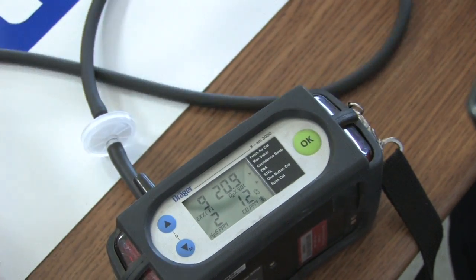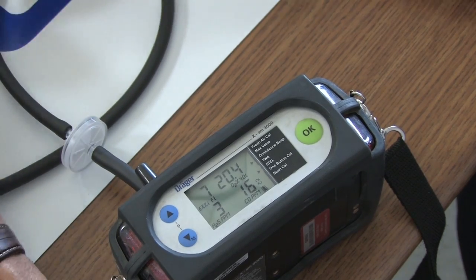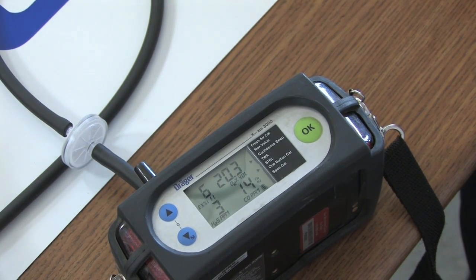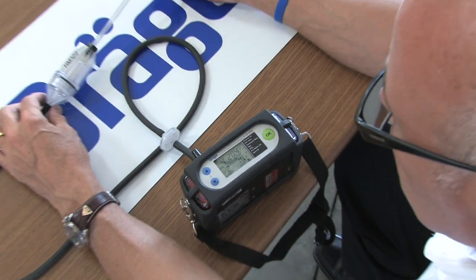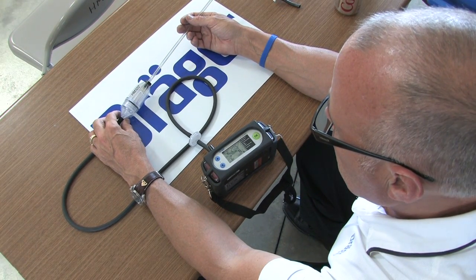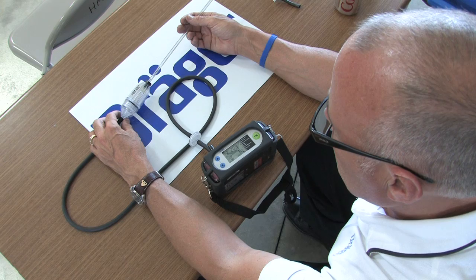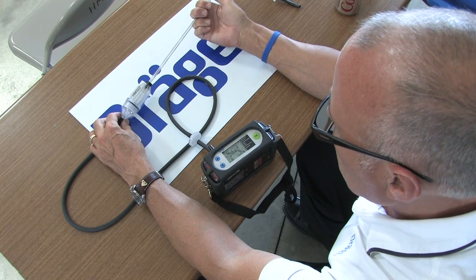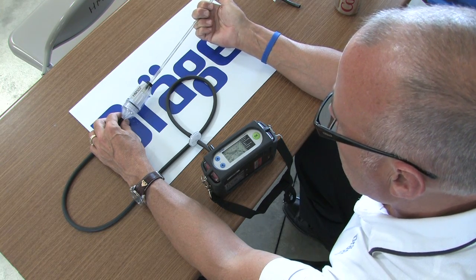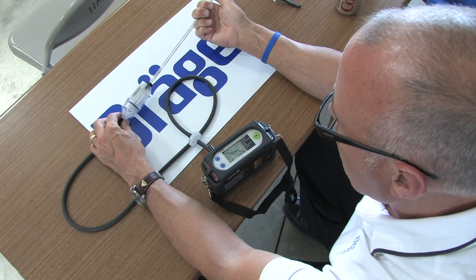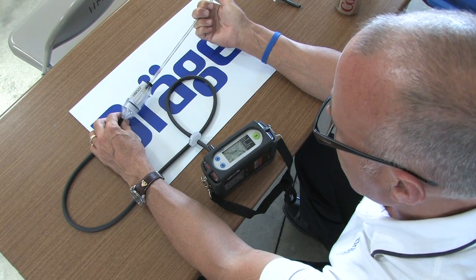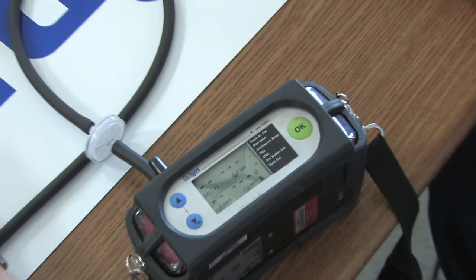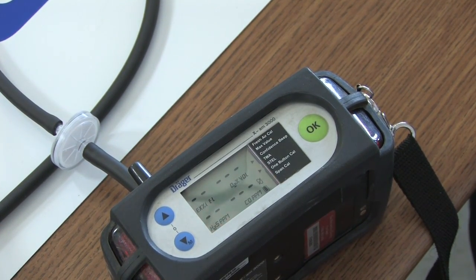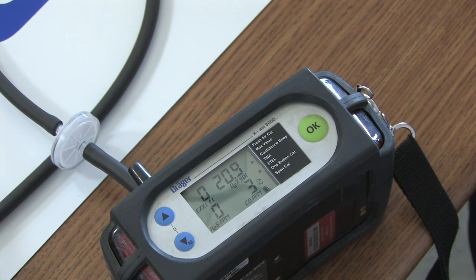And again, I'm going to run a flow fault on this pump. In the event that I come up on a space where I have to monitor remotely, I want to make sure my intake is at the tip of the probe. There's all the dashes again from a flow fault choke off. And notice the two little arrows now have a line through the middle of them stating that the pump is choked off. The moment I remove my thumb, back to normal operation.